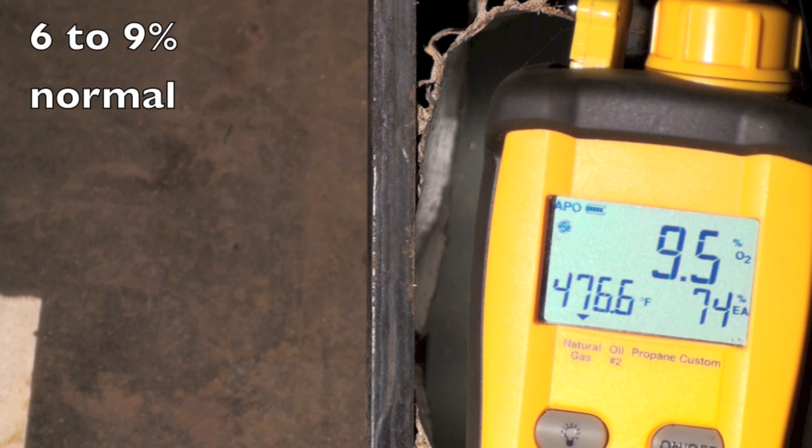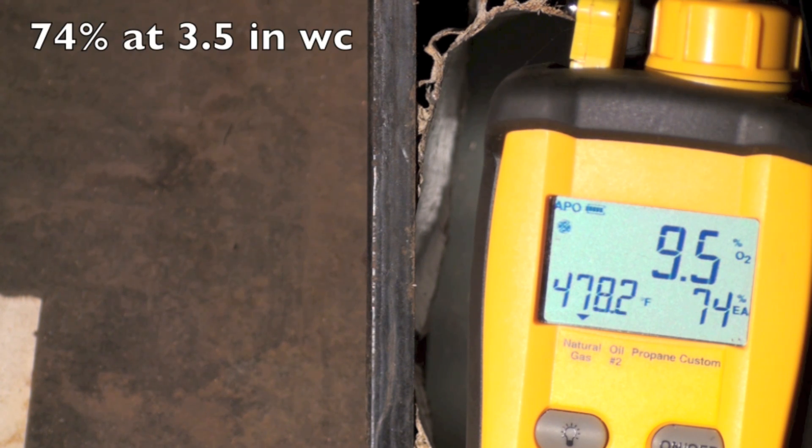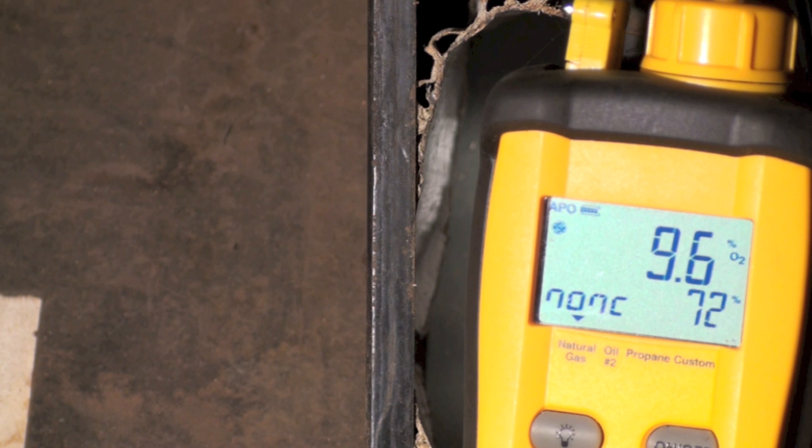My excess air is 74 percent. My stack temperature is down. Okay, let's see what the efficiency is. Okay, 72 percent.